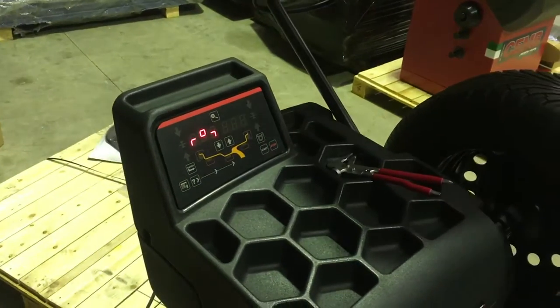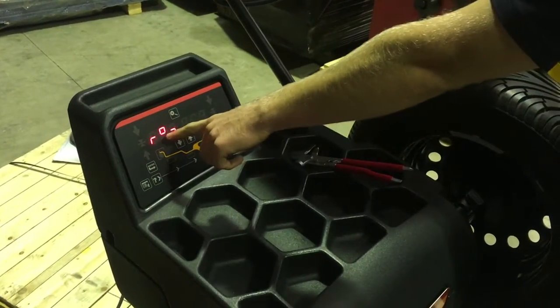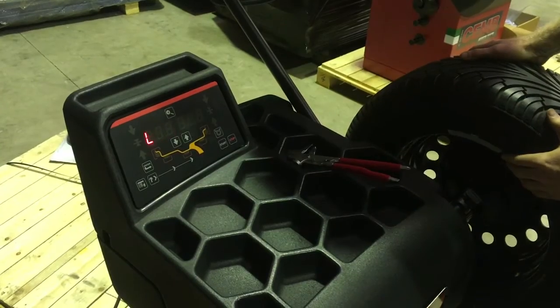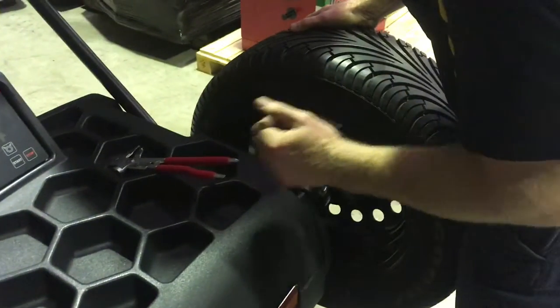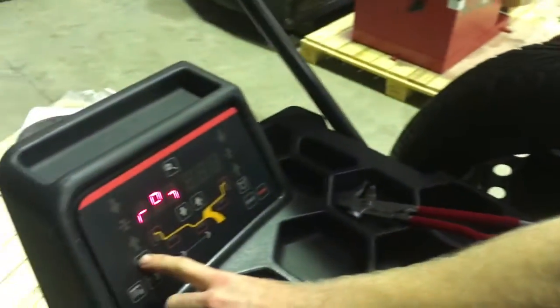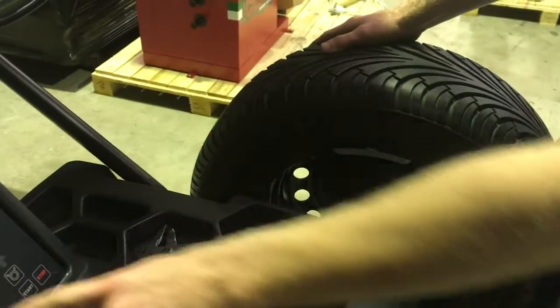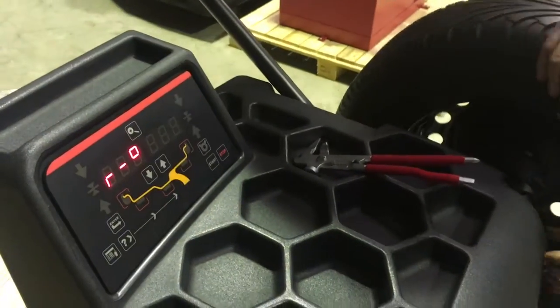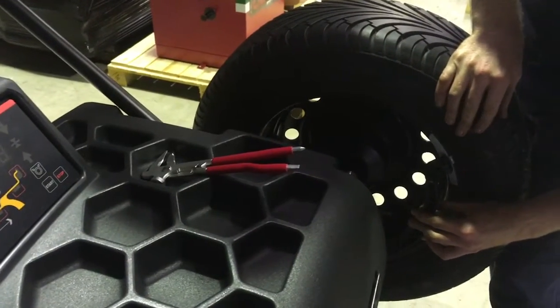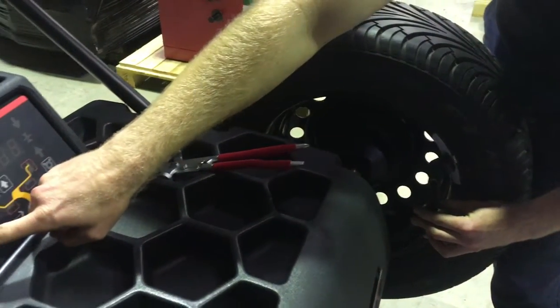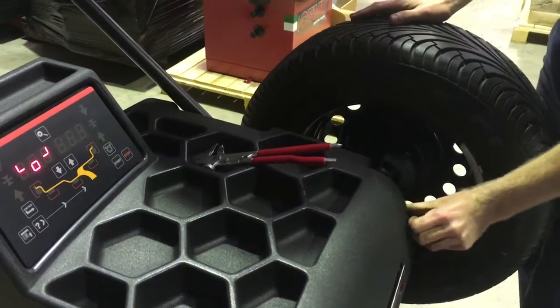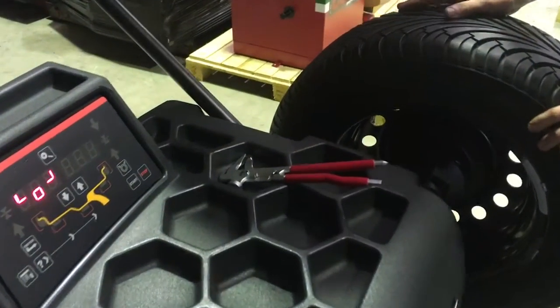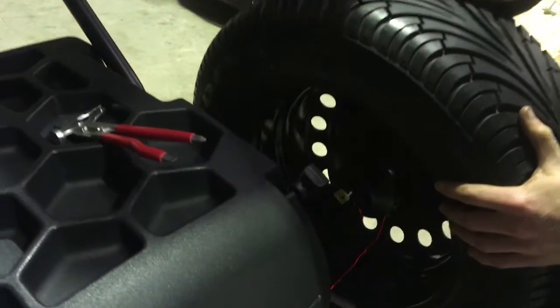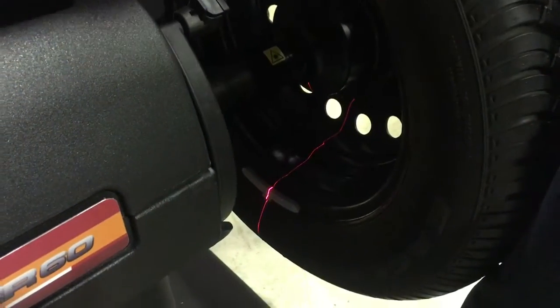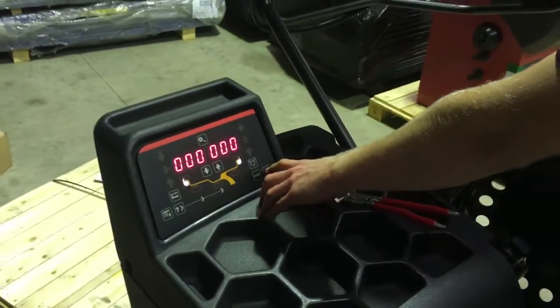Okay, after it's finished this spin, we'll see this symbol up here on the screen telling us to locate the weight at 12 o'clock. So we make sure the weight's at 12 o'clock, press the enter key. Then we'll see a different symbol, this one here, telling us to place the arm where the weight is. So we do that, press the enter key. Then finally we get this symbol here telling us to locate 6 o'clock. We roll it round to where the laser is pointing at the weight and press enter, and we're done. Press stop to get out of there.